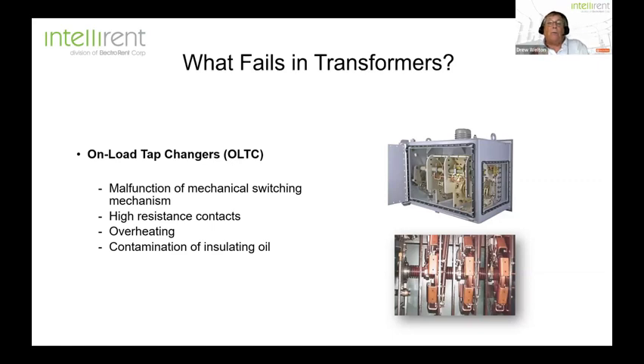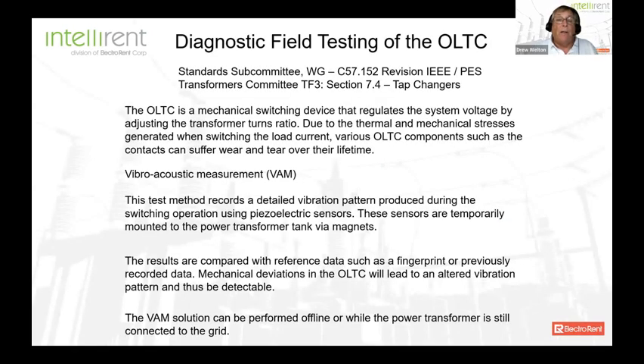Now finally, just to wrap things up, one of the weak points we talked about is the on-load tap changer. Malfunctions in the mechanical switching, high resistance contacts and overheating, and contamination of insulating oil can all lead to failure of your on-load tap changer. And a couple of the new industry standards in terms of advanced testing come from the Transformers Committee, C57.152, Section 7.4. This is the Guide to Field Testing, and it addresses some new approaches to testing and validating the health of your on-load tap changers.